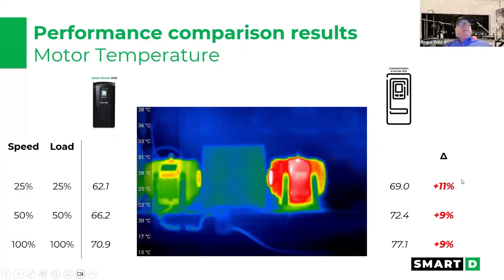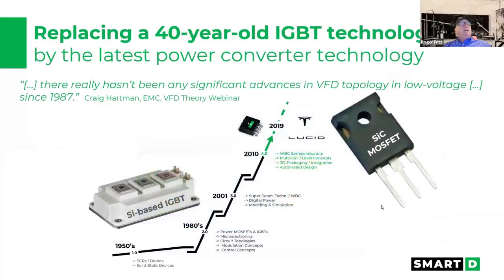You'll see that there's an 11% increase, 9% increase. That's why most motors with VFDs, they don't recommend you running into the service factor, which we have no problem with. You still get to use it. And what the real difference of the technology is, what they call this silicon carbide MOSFET controller.